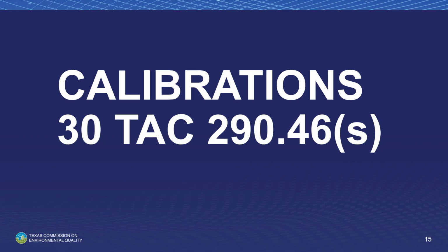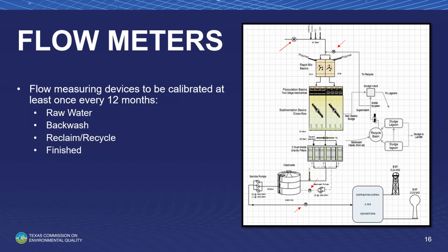Like I said, at a surface water plant, there's a lot more equipment that goes into that treatment process, which also means there are a lot more calibrations and verifications that need to be conducted on a variety of different timelines. Key difference here are your flow meters. There are typically about 4 different types of flow meters at a plant. There can be a lot more, especially when it comes to process control duties. But these flow measuring devices need to be calibrated at least once every 12 months. Typically, we'll see a raw water meter, a backwash meter, a reclaim or recycle meter if you're returning your wastewater to the front of the plant, and the finished water meter, so what you're sending out to distribution.